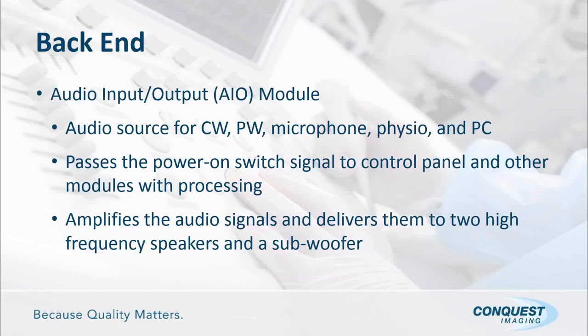You have an audio input-output module. And basically, it's kind of in the description. It's the audio source for your continuous wave, your pulse wave, physio, and any beep or bell that the PC wants to chime in on. One important part of this is it passes on the power on switch signal to the control panel, and we'll show you this in a future slide where you can actually see the path for the power on signal. But it's interesting that it goes through the AIO or audio input output module. So if you are having a problem with the system powering on, you certainly need to be aware that this board possibly can affect that. It also amplifies the audio signals going to 2 speakers and a subwoofer, so it takes care of that as well.